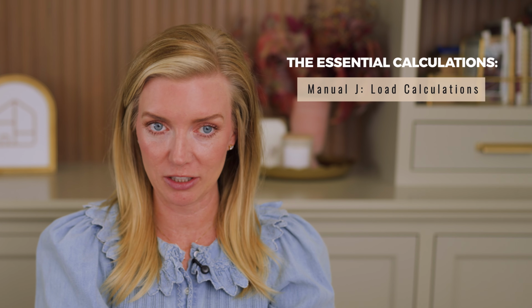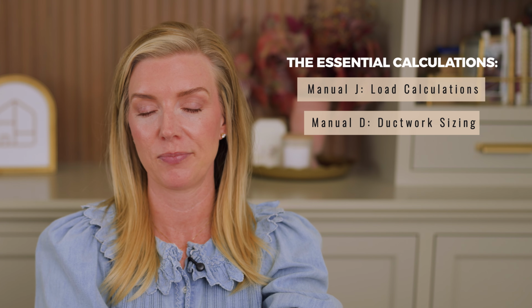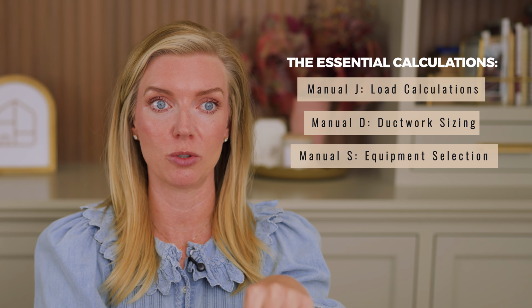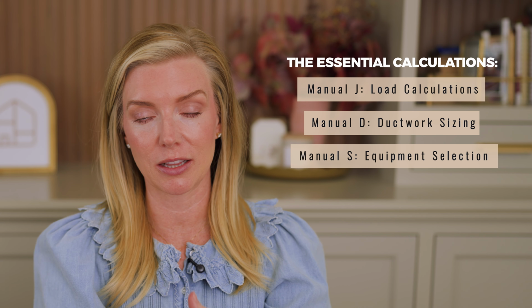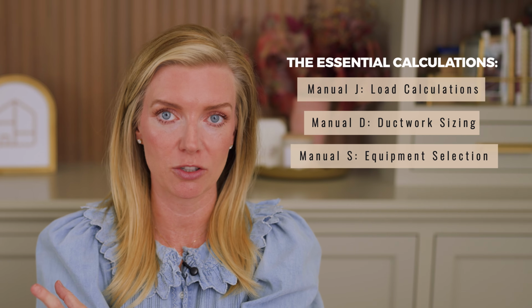There are other calculations too. There's a manual D that sizes the ductwork needed, and a manual S that determines equipment selection. So there's a whole set of mechanical plans, drawings, ideally even 3D images of the layout, and full specifications of the mechanical equipment that should be prioritized in the renovation or new build. If you're only hearing about square footage and tons, that's not enough data. Each state is a little different - some require a manual J calculation, some require all three. Here in California, we have Title 24, where you need all three of those calculations.